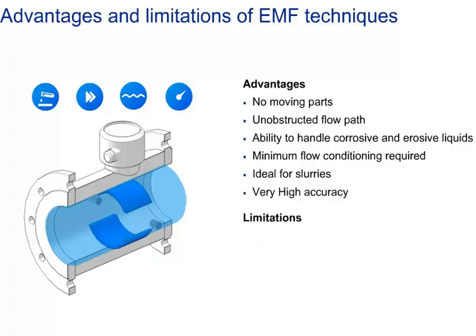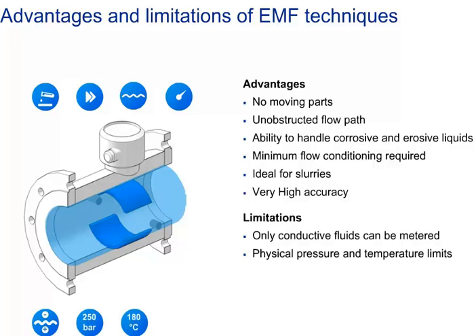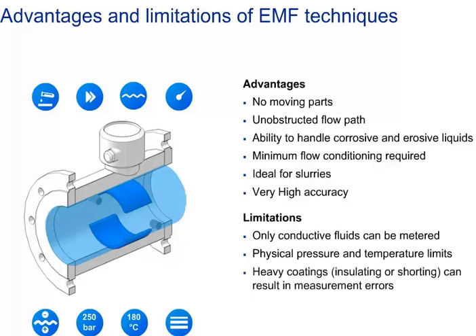Limitations include: only conductive fluids can be metered — minimum conductivity, depending on the meter design, is 5 to 20 micro Siemens per centimeter. Physical pressure and temperature limits apply: maximum pressure depending on the diameter is limited to 250 bar, and maximum temperature is limited to 180 degrees C. Heavy coatings, whether insulating or shorting, can result in measurement errors, e.g. water with high fat content.